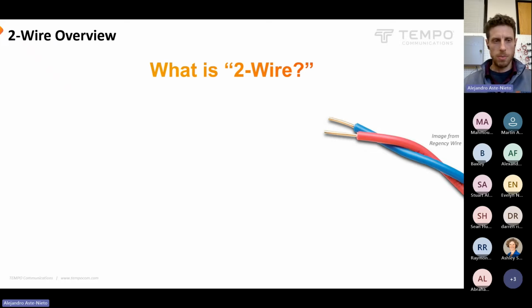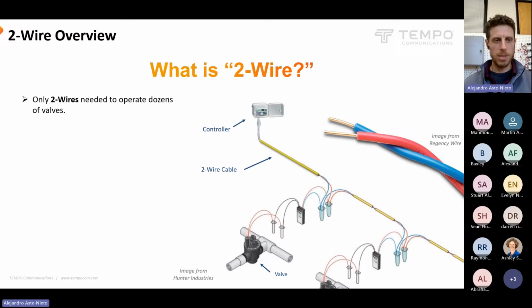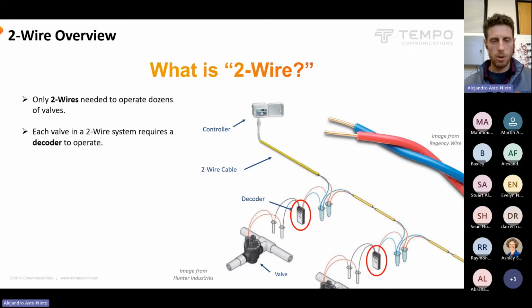What is two-wire? Well, it's two-wire for a reason. Only two wires are needed to operate many valves out in the field. So we have a controller, and we just have two wires coming out of the controller that can operate lots of these valves out there, as opposed to the more conventional system that has been around for longer, where there's a wire going to each valve. In this kind of system, a decoder is required to operate a valve. So it's kind of acting as a middleman between the controller and the valve itself.